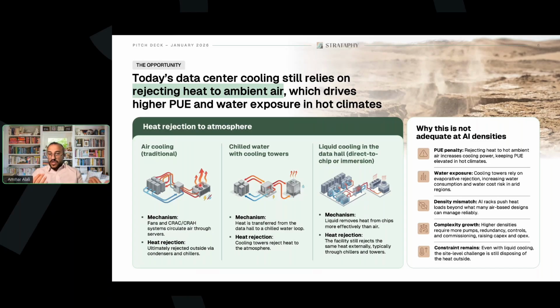The second method is chilled water with a cooling tower. This is what's typically referred to as district cooling. Same mechanics, compression and expansion valves, but the condenser, or the heat rejection function, utilizes a heat exchanger between, let's call it, the hot loop and the cold loop. The cold loop is where you're taking the heat to get it cooler. That's the condenser. This condenser loop takes it to something called a cooling tower that looks something like this. This cooling tower uses evaporation as a method to dissipate heat. So you're evaporating part of the water to make the water return cooler. Then it goes back to the condenser, and that's how you reject heat from your cooling cycle.